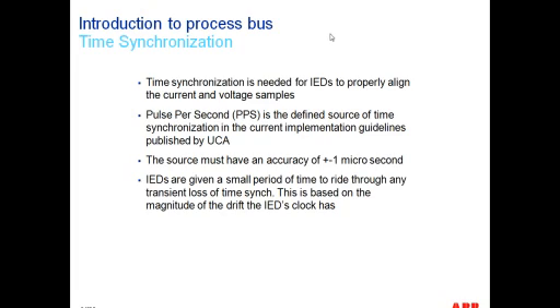I have another question here which says, is the 61850 being used for transmission as well as distribution? 61850, at least when we refer to protocols, is really about client server, which is something similar to DNP within the substation. It refers to GOOSE messages, which is the high-speed or real-time exchange of information between relays. And then it also relates to the topic of today's webinar, which is sampled measured values, or the process bus. We have found installations around the world at transmission, distribution, as well as generation plants.